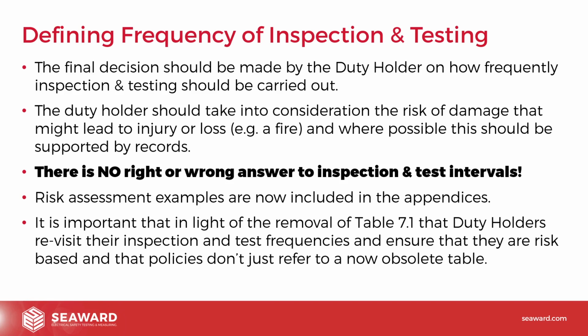So risk assessment examples have now been included in the appendices. If you have a look in the appendices at the back of the Code of Practice, you'll see a couple of different scenarios there where they've carried out risk assessments, and that just gives you a rough idea of the things you need to look at and maybe how you carry out your own risk assessments. It's important that, in light of the removal of Table 7.1, duty holders revisit their inspection and test frequencies and ensure that they are risk-based, and that policies don't just refer to now obsolete tables. So your risk assessment policy, or your customer's PAT testing policy, might just say, well, we test according to Table 7.1 in the Code of Practice. There now is no Table 7.1. So they may need to look again and make sure that they have actually risk assessed the frequencies rather than just picking them from a table which has now disappeared.